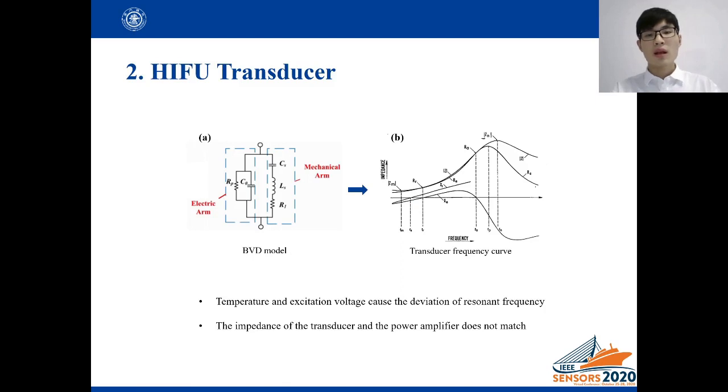The transducer is a very important component. The impedance of the transducers operated at a resonant frequency can be well explained by the Butterworth Van Dyke model as shown in figure A. It can well simulate the impedance variation of transducer with the frequency as shown in figure B.